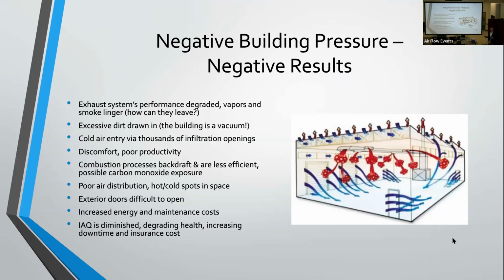The same thing is happening with your buildings, except rather than holes in the side of the box, your air is being pulled in from thousands of infiltration openings throughout the building: wall openings around doors, windows, and so forth. That creates negative pressure in the space and pulls all that air in. You're pulling dirty air into the space, which isn't good. You're creating drafts and cold spots, which can lead to employee discomfort and reduced productivity. With naturally vented appliances like furnaces, unit heaters, and boilers, a negative space can cause backdrafting, which can cause carbon monoxide exposure if it's bad enough.